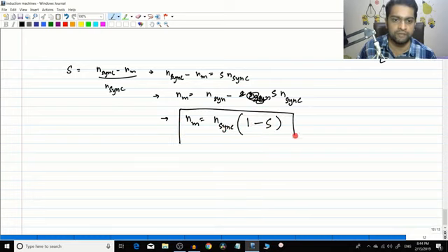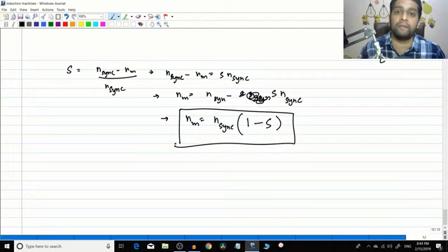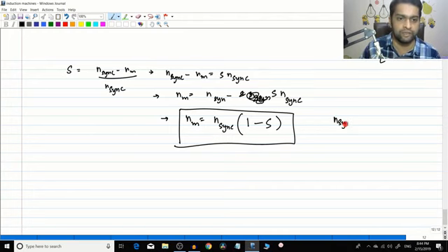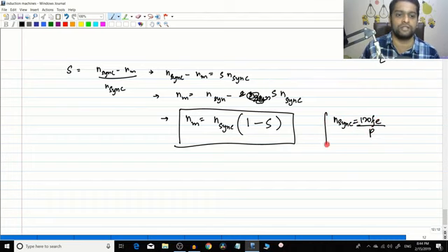This is a very important relation, because usually the nameplate of the induction motor gives the slip value, and from it you can find the speed of the motor. For example, somebody tells you that the slip is 0.04. What is the rotor speed? N sync is equal to 120 F electrical divided by P, which is constant for a motor.